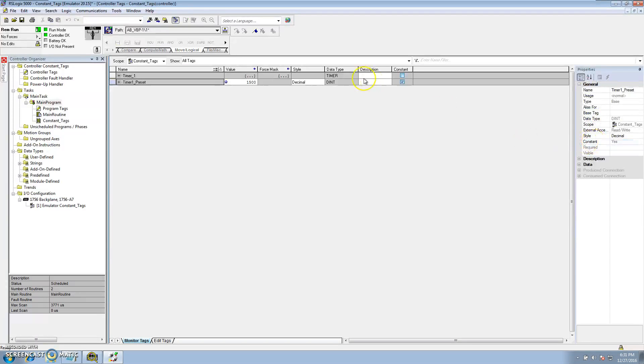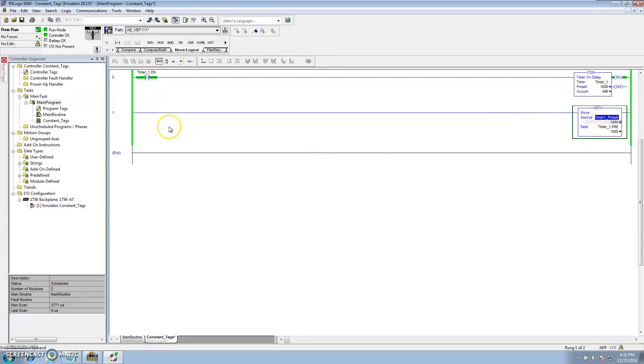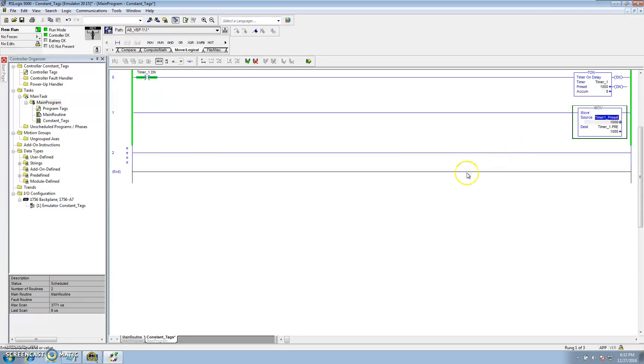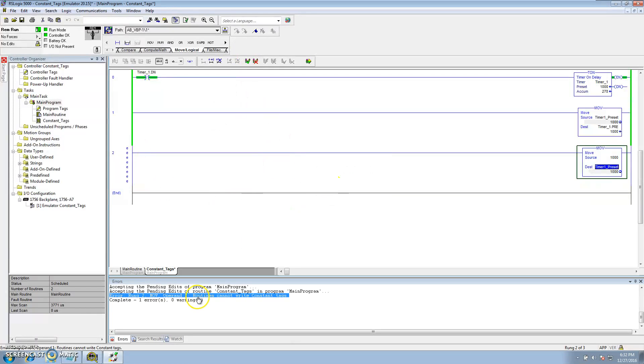If I make it a constant tag, I cannot change it inline — I am forced to go to Monitor Tags to change it there. I use constant tags a lot for servo attributes; if I want a speed value and I don't want that speed to be changed, I use a constant tag. Note that in a routine you cannot write to a constant tag — if you try to put another move to write a set value into it, it will not allow it.